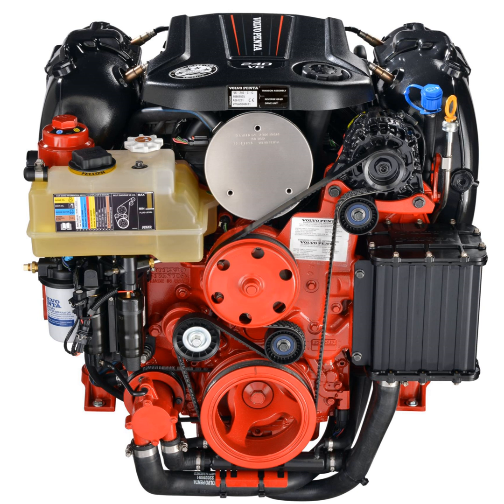It's the combination of the long-term data with the instantaneous data—watching your coolant temperature and oil pressure over the lifetime logged by the engine hours. The real power isn't just knowing your temp right now; it's noticing that over hundreds of hours, your normal operating temp has slowly crept up by 5 degrees. That's your early warning, the trend that tells you it's time for service before a small issue becomes a massive engine-killing failure down the line. That's the real power of having this much accurate data at your fingertips.